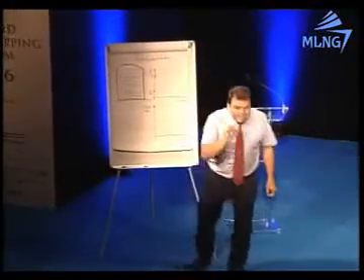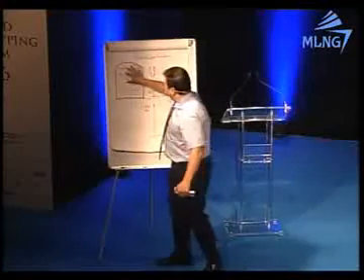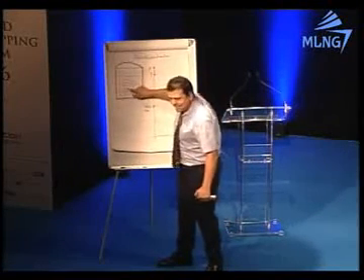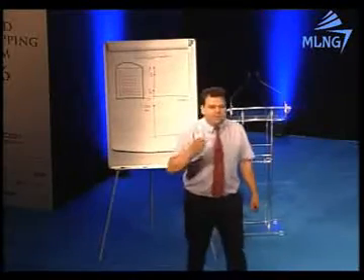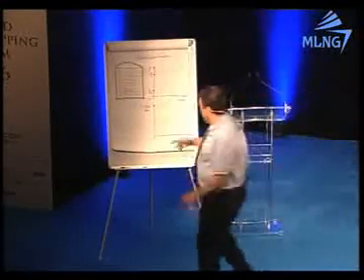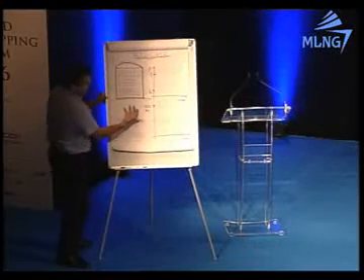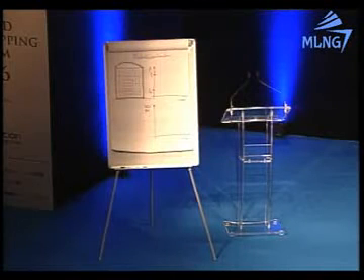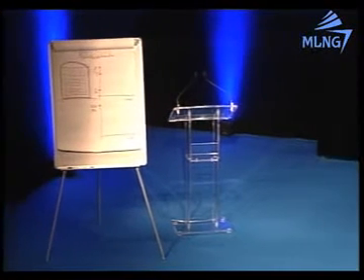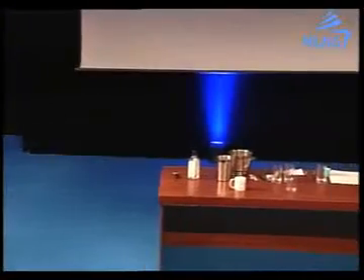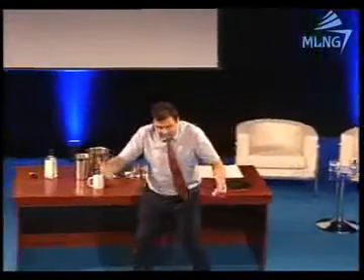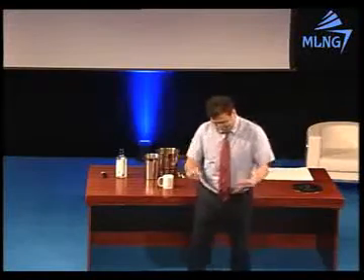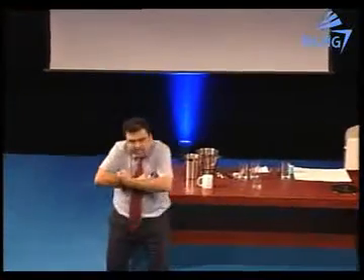From the very beginning, when the carrier finishes, the lower LNG will become a superheated fluid, like the cup of coffee, because we have heat coming from the ground and from the ambient air, and the upper layer is like a lid. The upper layer does not allow the lower LNG to boil. So with time, the lower LNG has more energy, but it cannot boil.